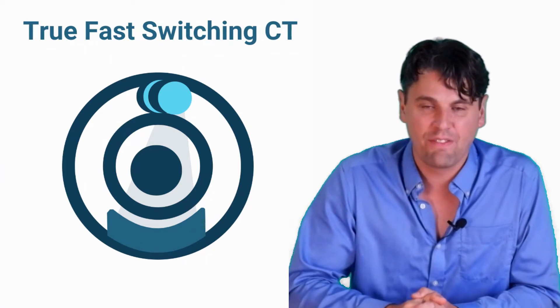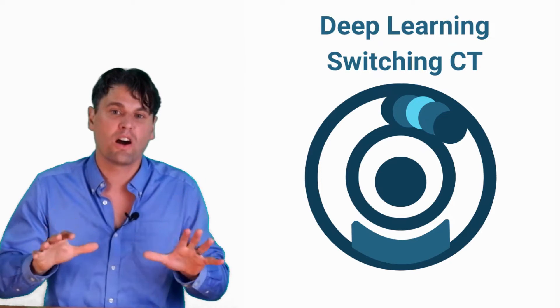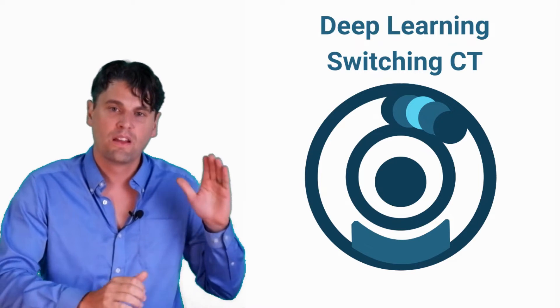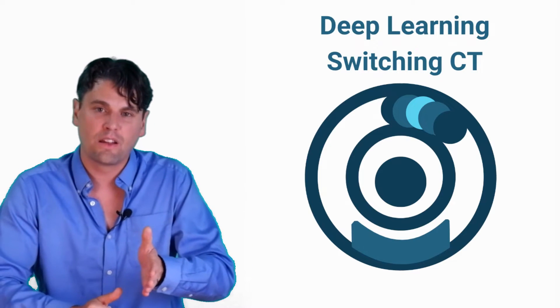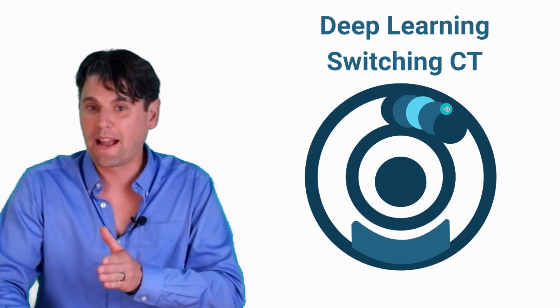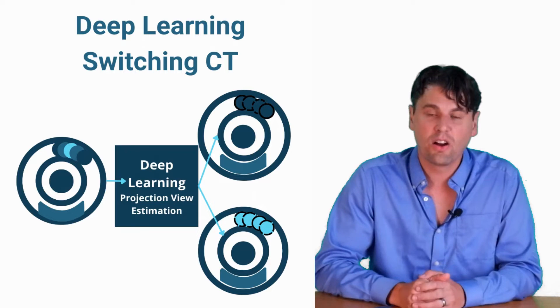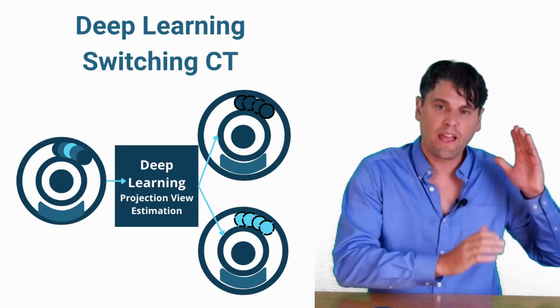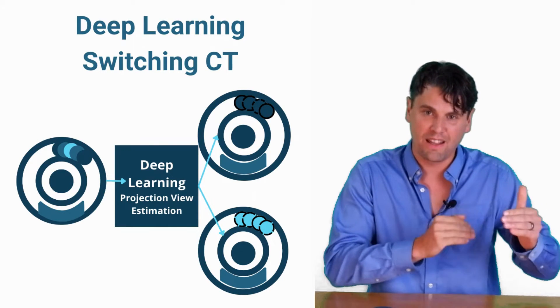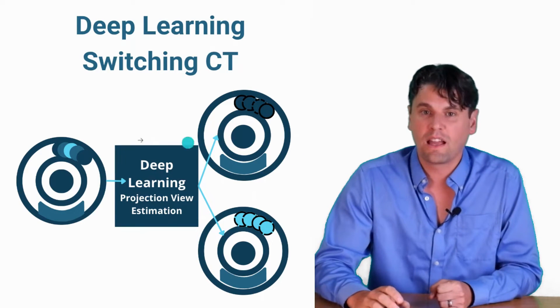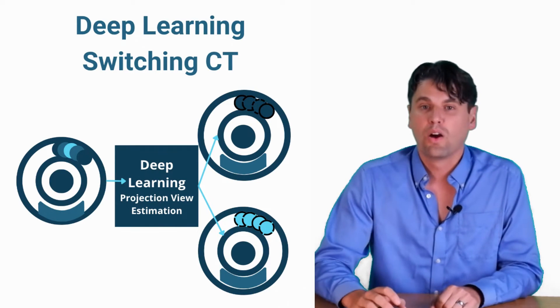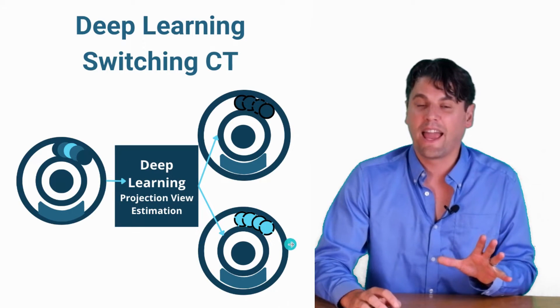That is what we call true fast KVP switching. Recently, the concept has been productized to do what we call deep learning switching. In this scenario, the tube hardware can't switch fast enough to go every other view, but you can still modulate the KVP more slowly — changing from a high KVP to a low KVP over several views. You then use a deep learning algorithm to estimate in the projection space what it would look like if you had true alternating low KVP and high KVP projections.